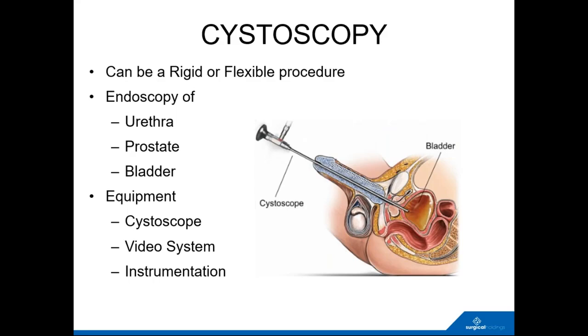And I mentioned before, in terms of the direction of view, in the cystoscope it can be 0, 12 degrees, 30 degrees, 70 or 80 degrees. That basically means a 0 would be flat at the distal tip, 30 is forward oblique viewing, and then sideways viewing would be 70 or 80. And you'd interchange these cystoscopes through the sheath. This is actually an incorrect diagram because it doesn't actually have a sheath. But you'd interchange cystoscopes, take a 30 out, or a 0 or a 12, and then put in a 70 or an 80 to look at the bladder neck.